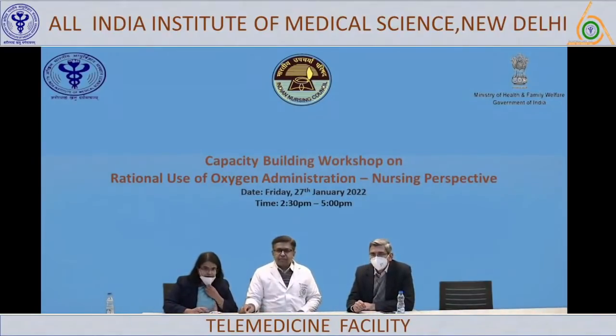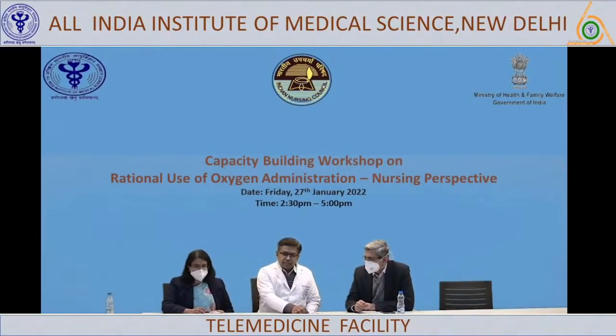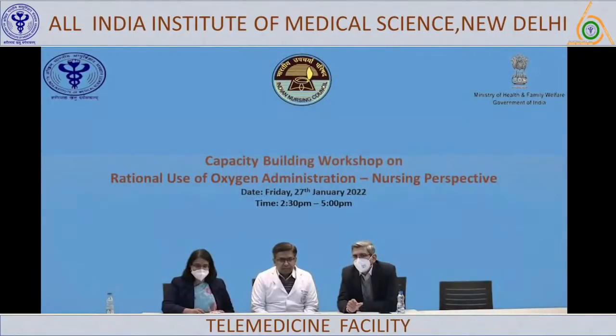Rakesh, the empty cylinders should be labeled and kept separately from the filled cylinders. Yes, sir. The new cylinders that come in have a seal on their outlet, and if the seal is removed, one needs to be careful that these are not mixed up, and one shouldn't think that we just have a cylinder. Therefore, part of the monitoring and daily checks that a unit should do is to look at whether there is at least one full cylinder, particularly for transport. For areas which rely primarily on cylinders to deliver oxygen, they need to have an adequate inventory of full oxygen cylinders available with them.